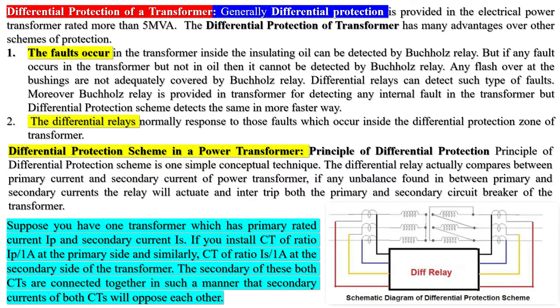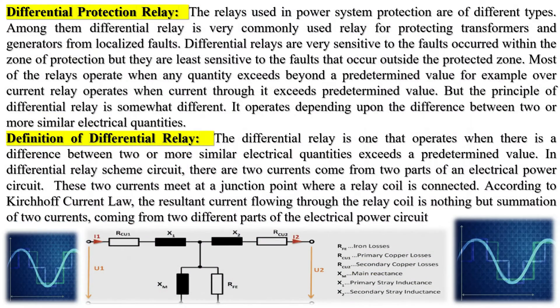Differential protection operates on the principle of current conservation, where the incoming current must equal the outgoing current. However, a key distinction arises when dealing with transformers: the currents at the high-voltage HV and low-voltage LV sides are not equal. Therefore, we must apply a transformation ratio to calculate the differential current between the HV and LV windings.